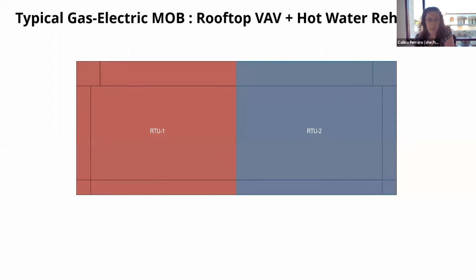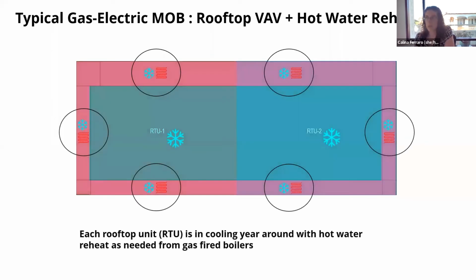The challenge is that when the building actually operates, dividing it just in half with that zoning means the rooftop units on each half have a large interior zone that never sees the outside. It only sees people, computers, and lights in there, so it's always going to need cooling. Whereas the perimeter zones, like we saw from the climate profile, get cool winters, evenings, and mornings too, so we'll need to be heating those spaces while we're cooling the interior.